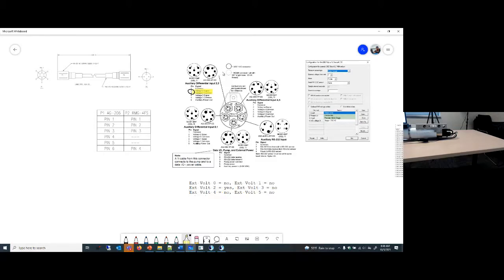So what we're going to be going over here is how to create an XMLCon configuration file. That's this guy right here. This configuration file is correct for the particular CTD that I have. The temperature, conductivity, pressure, and oxygen calibration coefficients are correct, and all the settings match here.